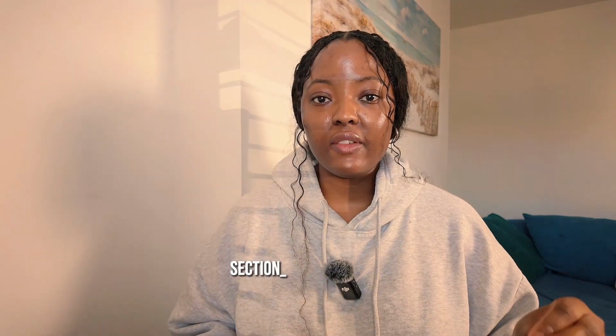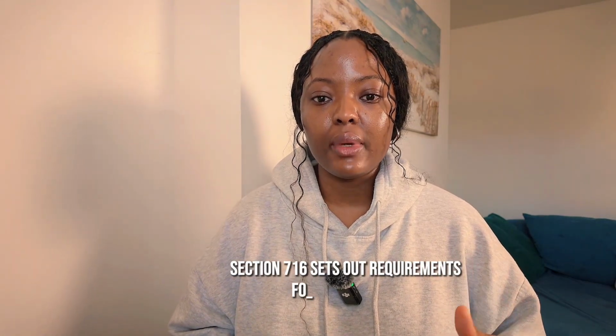However, Amendment 4 changes that. Section 716 sets out requirements for distributing extra low voltage DC power using data cables. It addresses cable derating, because when you use a bundle of PoE data cables, you get heat buildup, and that affects the current carrying capacity of the cable.